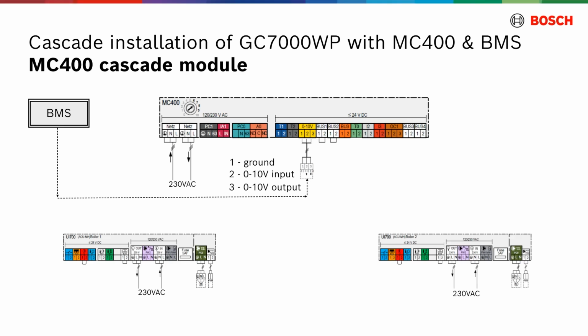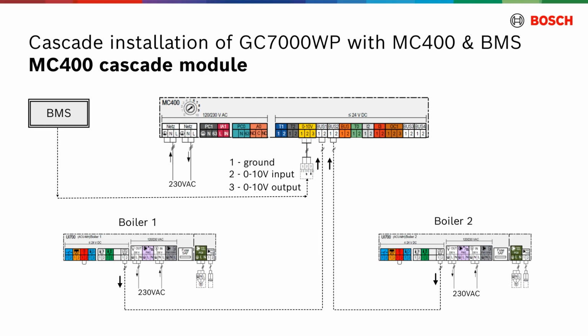As mentioned above, the first GC7000WP boiler must be connected to the bus 1 terminal, the second boiler to the bus 2 terminal, and the strategy sensor to the terminal T0 of the MC400 Cascade module. The connection for the boiler pump PC0 is located in the pump connection box at the bottom of the GC7000WP.